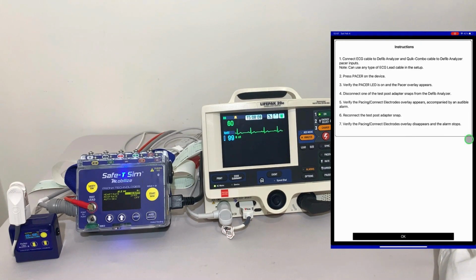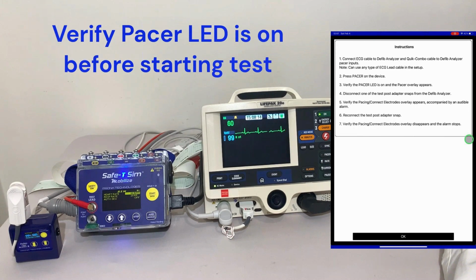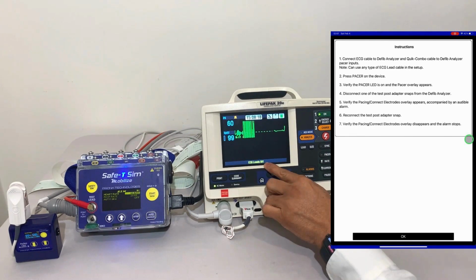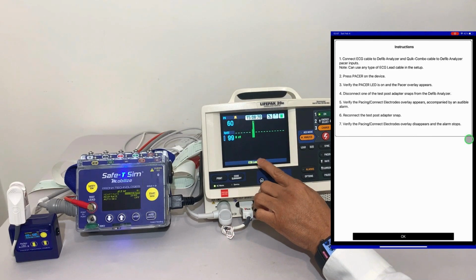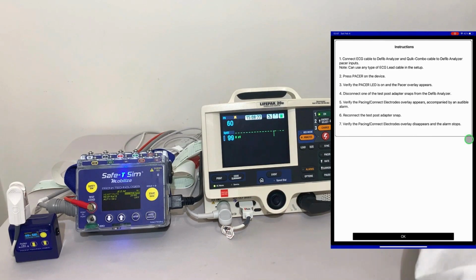Part of this instruction is to make sure that we can detect a leads off condition for pacing before we do the test. So it's simply removing one of the ECG leads from the device, from the analyzer, and confirming we see the alert on the defib that the leads are off. So we can see that it's working properly to confirm that indeed it is detecting that.